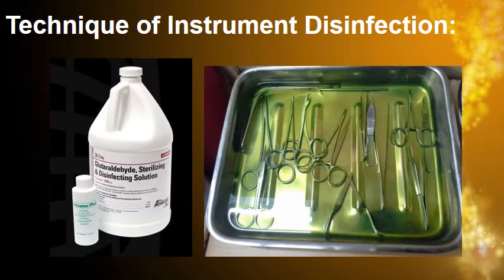The exact procedure for the disinfection will be as follows. The disinfectant agent should be formulated and diluted according to the manufacturer. The instructions of the manufacturer should be followed completely. After I clean and wash the instrument, I put the disinfectant solution in the tray and submerge all the instruments.